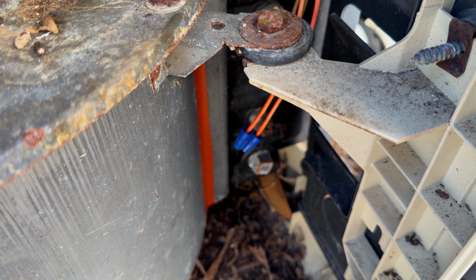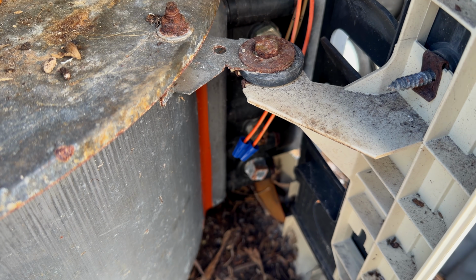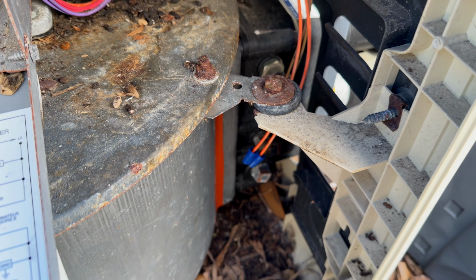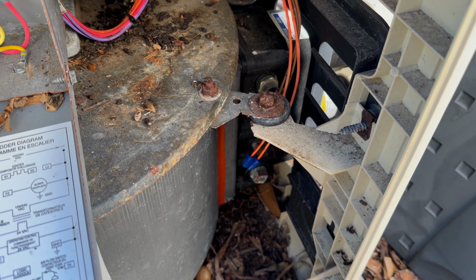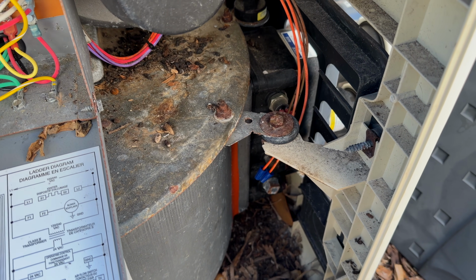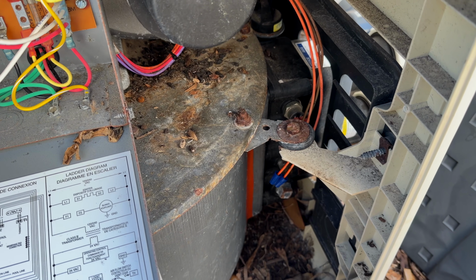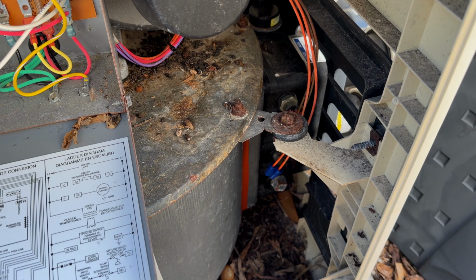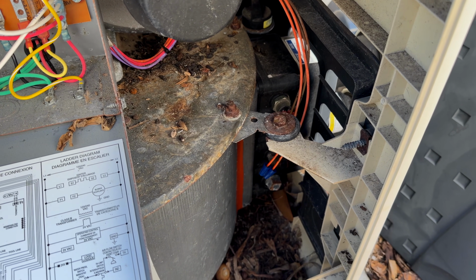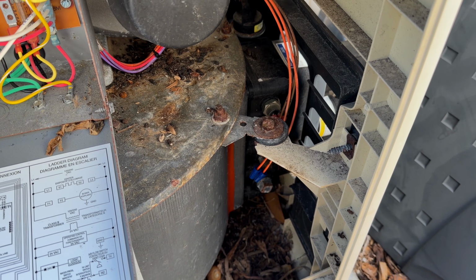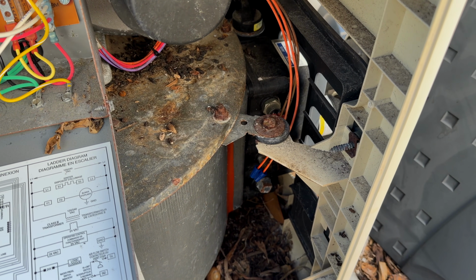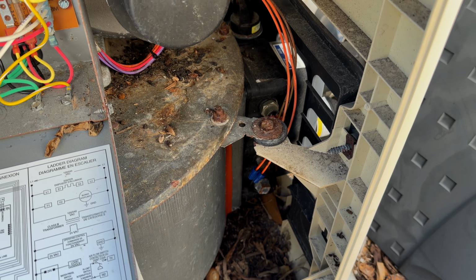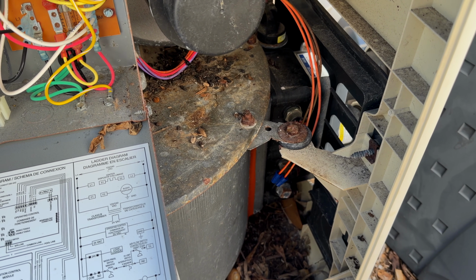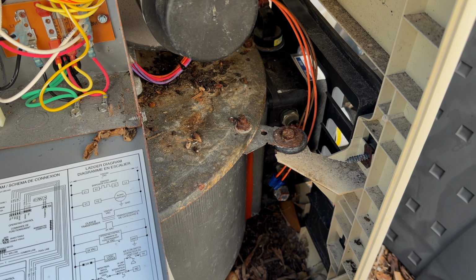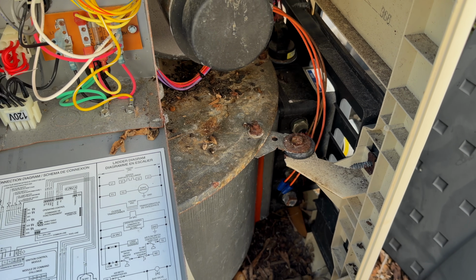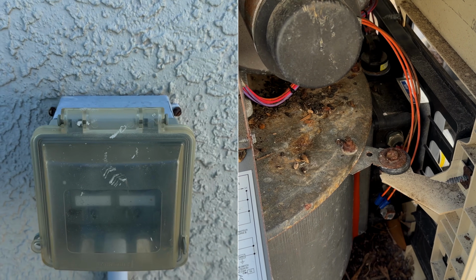So there is a quick way to verify if it's just the high limit switch, because what happens with some of these heater diagnoses is it'll be a code for a temp sensor, replace a temp sensor, but that's the first thing in the sequence to make this heater fire. And then from there, it goes through a sequence of things. So you could run into six or seven other issues once you replace that temp sensor. So you want to try to verify if the one problem is the problem, to make sure the heater works, so you're not just throwing parts at an old failing heater. So I got a workaround for this. I'm about to show you right now.